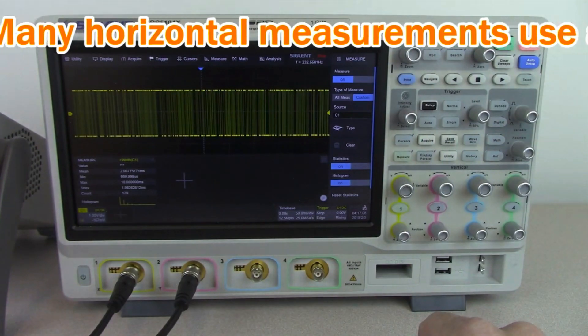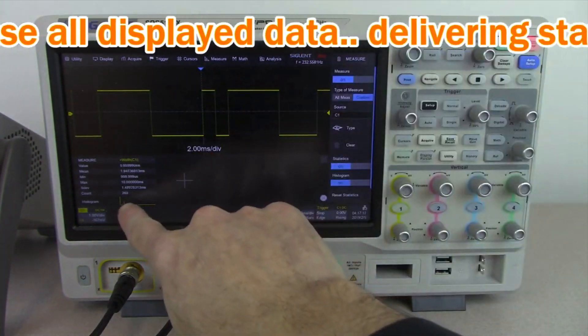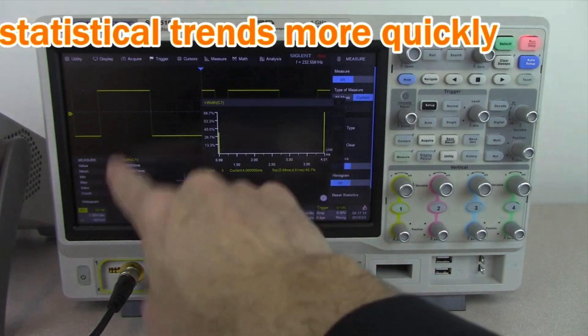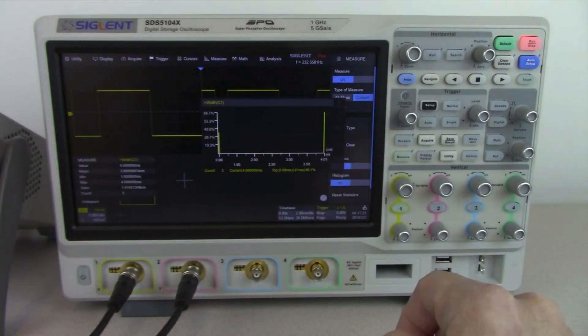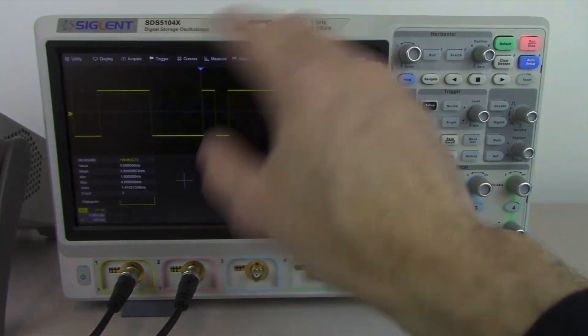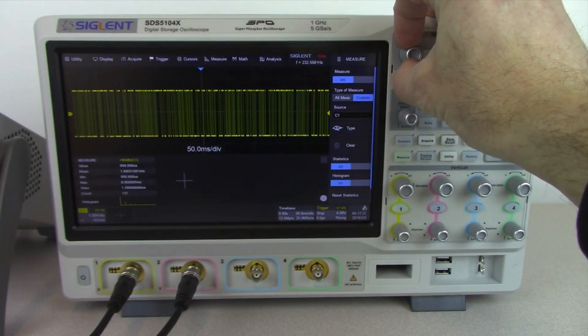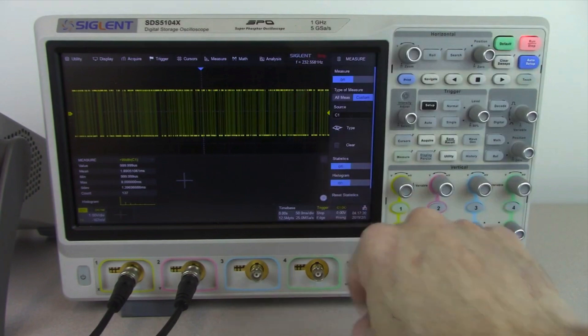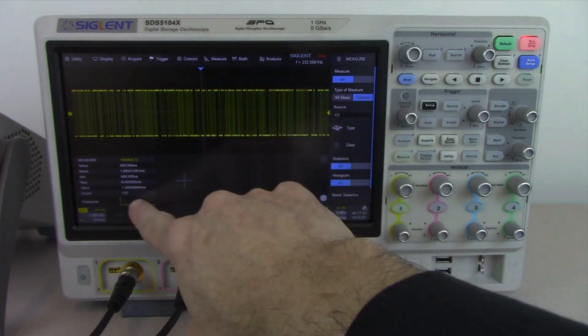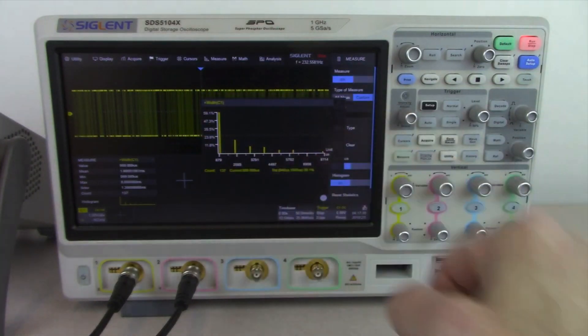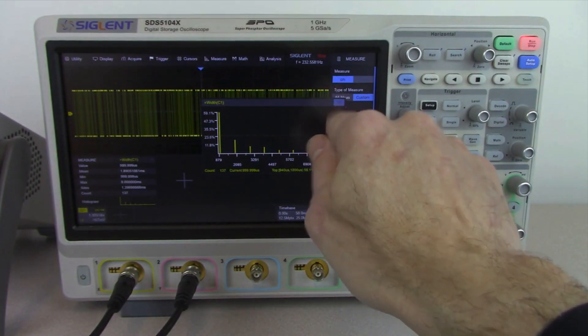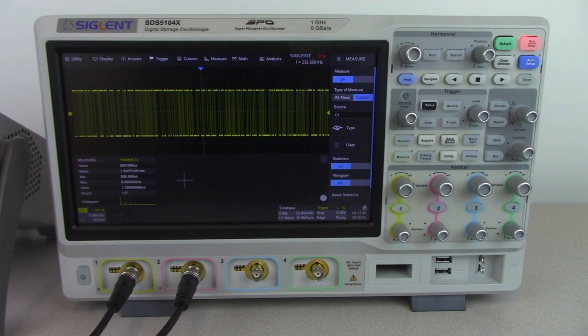We can update with single acquisition, shrink down the view, and reset the statistics. Now we only have three full pulses — one, two, three — and we can see their individual pulse widths on the display. Whatever we have on the display, up to 1000 measurements, we can calculate. After resetting, we've now got 137 pulses. In this way, you can use it as a pulse counter as well as a pulse discriminator to see exactly what your pulse widths are in a particular sample.